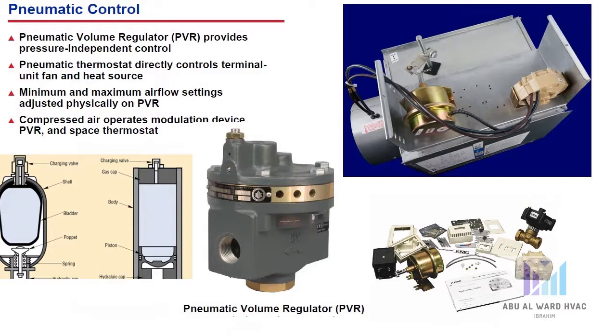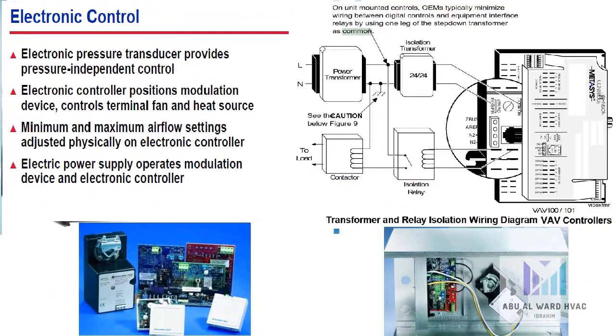A pneumatic volume regulator (PVR) provides pressure independent control of the VAV terminal unit. The PVR is connected to the airflow measurement device and the pneumatic space thermostat. The PVR directs the actuator to position the modulation device to deliver the required airflow to the space. The pneumatic thermostat signal is used to reset the airflow set point and directly controls the terminal fan and heat source. Minimum and maximum airflow settings are physically adjusted on the PVR. Compressed air is required to operate the modulation device and to power the PVR and the space thermostat.